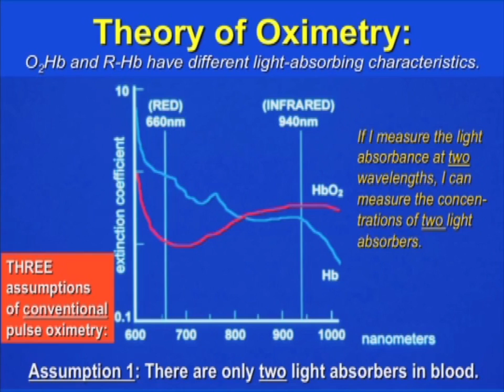Assumption number one, conventional pulse oximeters, conventional is underlined here for a reason because we're going to talk about more advanced pulse oximeters in a few moments. Conventional pulse oximeters have only two wavelengths of light, therefore they can only measure two absorbers in the blood, therefore there can only be two light absorbers in the blood for a conventional pulse oximeter to work, and those two absorbers are assumed to be reduced hemoglobin and oxyhemoglobin. There's nothing else there.